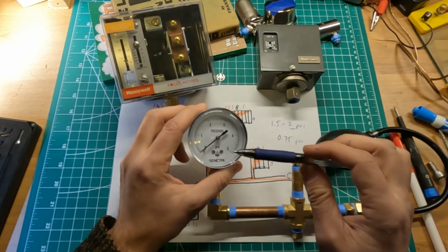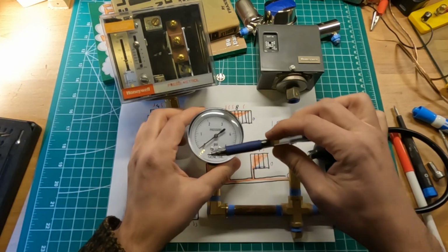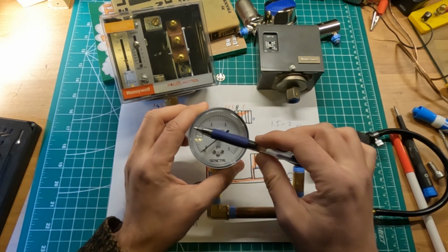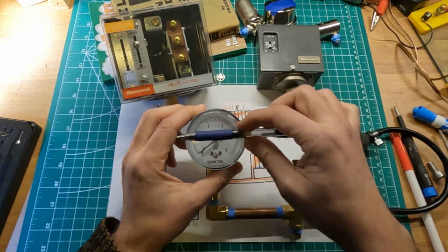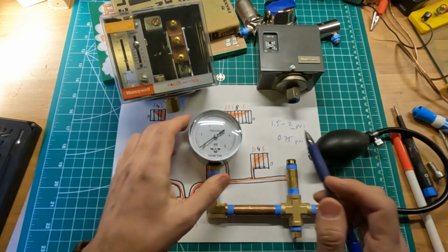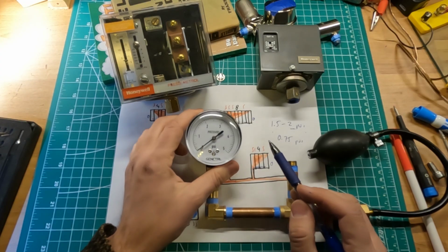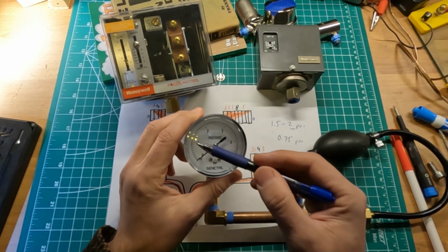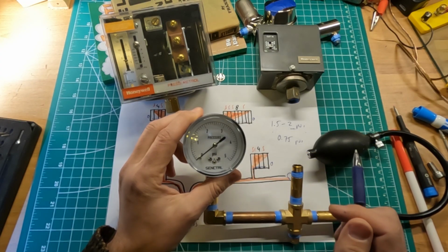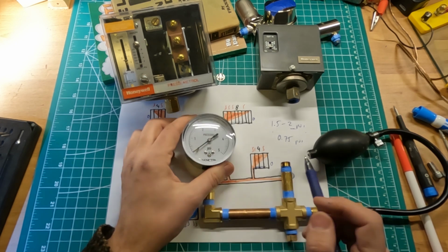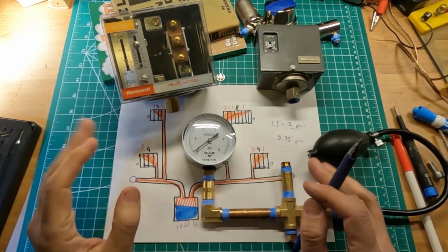Now, if your system is decently working, you will see that from 0 to the proverbial 1 psi, this buildup is going to go slowly. I measured on my specific system in my home, from 0 to 1, I think I measured something like a 3-minute buildup. So that means I have a decent working system, and the pressure buildup is not super fast.